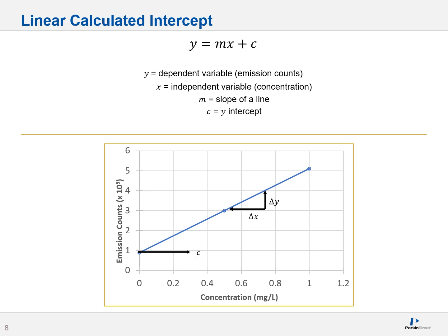The y-intercept here is not forced. What do I mean? I am not jamming it through a certain point. In a linear calculated intercept, the y-intercept is calculated by the other points. The curve ends up on the y-axis wherever it wants to. This kind of curve is often used in clean and low concentration applications, usually in GC, LC, UV-Vis, depends upon what you're doing.